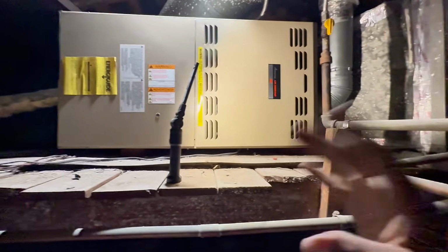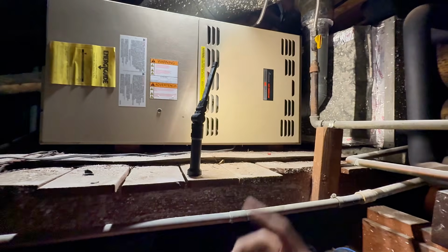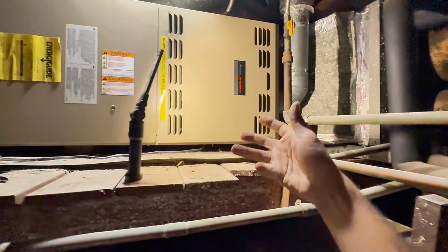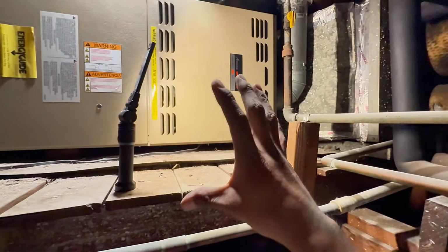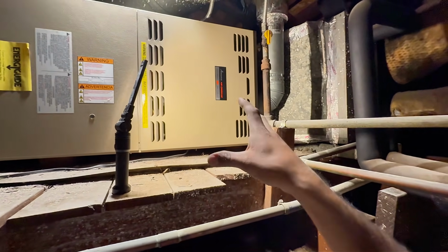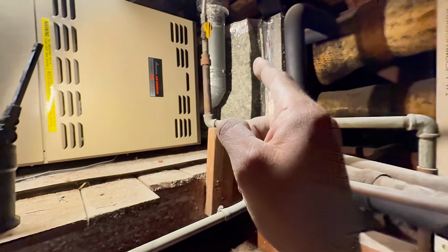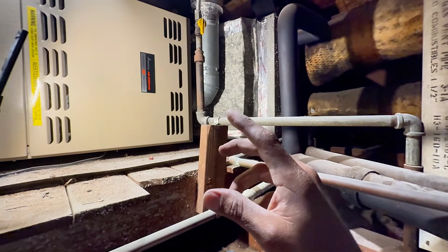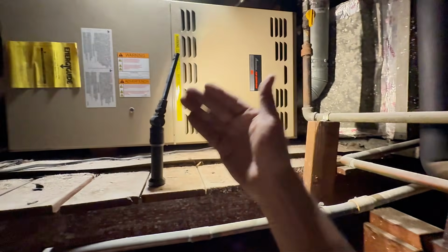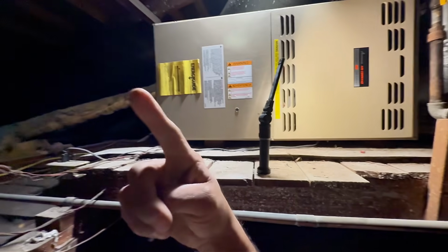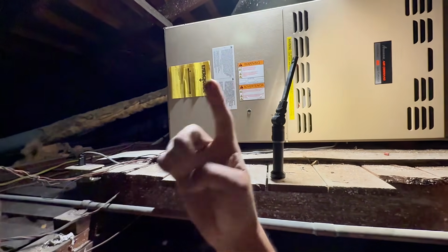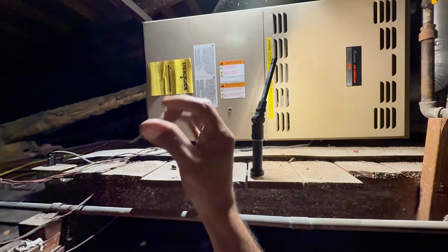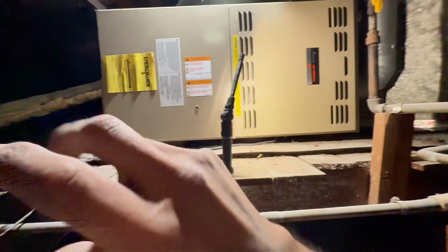So typically in commercial industrial systems, you'll hear terms like DX, direct cooling, and indirect cooling. From what I understand, direct cooling, which is what we deal with in residential, like commercial, is where you have the return air actually making an impact and touching the piping where the refrigerant is at. We do that every day, right? Warm air, boom, hits that evaporator full of refrigerant. But indirect cooling is where your evaporator is somewhere else, and over there in the other unit you have water transferring. You have that water basically coming back cold this way.